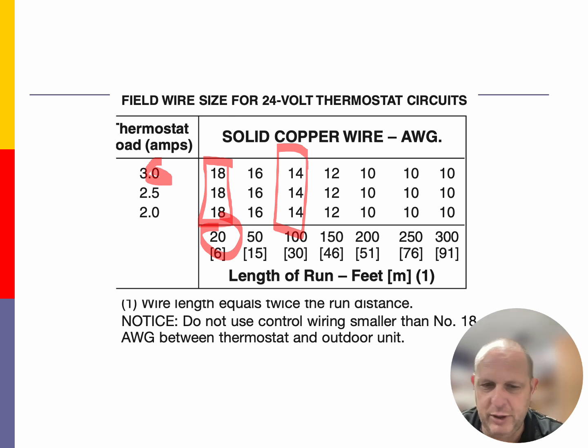Although the graph that I am showing you here happens to be from a Rheem distributor telling us that if we run a significant run length for a control wire, we need to up the actual size of that control wire. We can see down here, do not use control wire smaller than 18 gauge control wire for these particular units. Like I said before, never really had a problem with these particular units running an 18 gauge control wire.